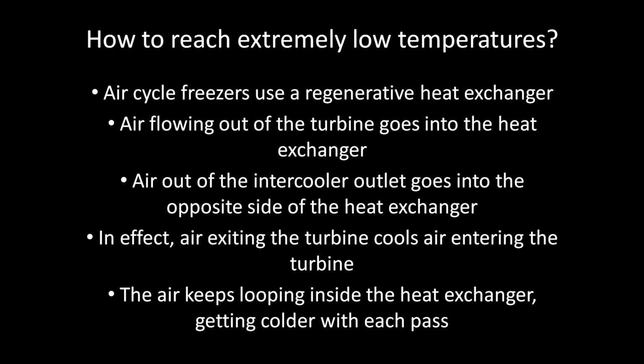Just a few more thoughts. So how do they reach extremely low temperatures with an air cycle machine? Well, there's these air cycle freezers, and there's a lot of tricks that these people have up their sleeves to make it work. But primarily, it uses this really neat heat exchanger. It's a regenerative heat exchanger. And basically, air that's flowing out of the turbine goes into one side of the heat exchanger, and the air coming out of the intercooler goes into the opposite side.